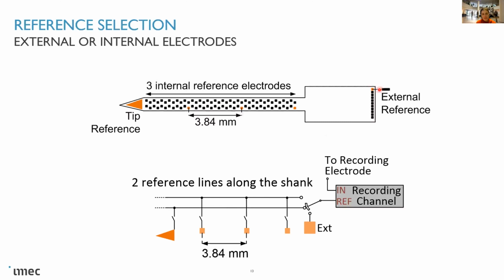And we have the possibility to connect an external electrode as well. So each channel can select which of the 3 references to use. And in software you can use this selectivity to establish which reference to assign to each channel. Normally in practice, you select the same reference for all channels. I haven't seen any practical reason why you would do differently.